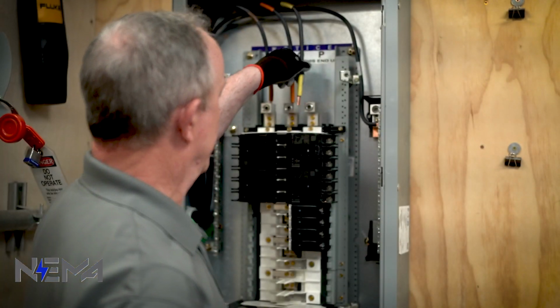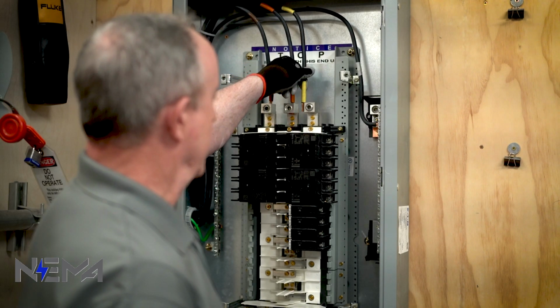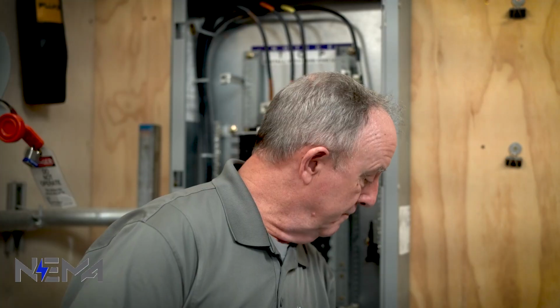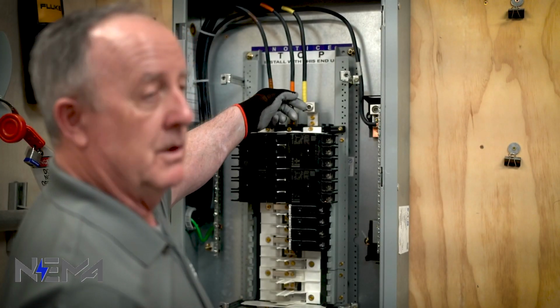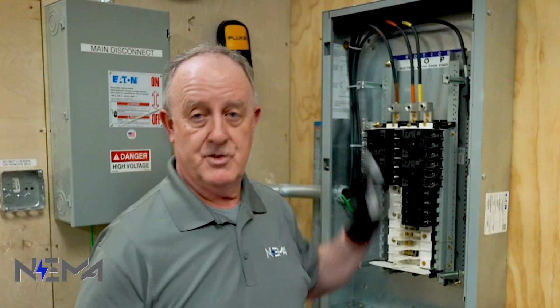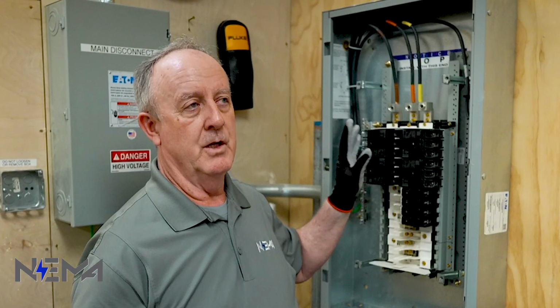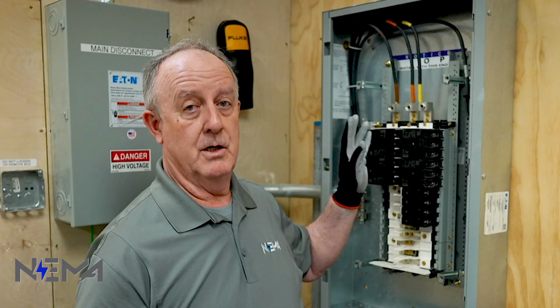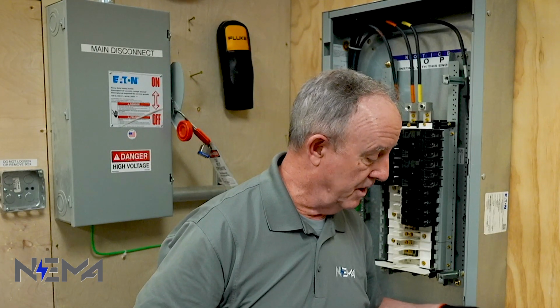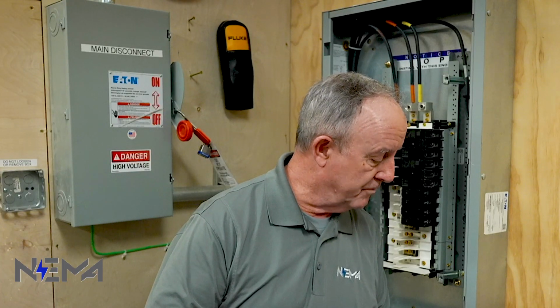So you want to properly strip and prepare the conductors to make the termination, and we've done that. We've stripped this copper conductor here. It's nice and clean. It's ready to be installed. And one thing you want to make sure of when you make this connection is, in our example, we have a hex head set screw connector, so we have the correct size hex head to go in there. But sometimes you'll have a slotted screw or even a Phillips head connector. Then you want to make sure you use the correct size slotted or Phillips screwdriver, again a torque measuring screwdriver, to make that connection. Otherwise, you run the risk of not getting the proper torque on there, and you can also damage the connector itself.